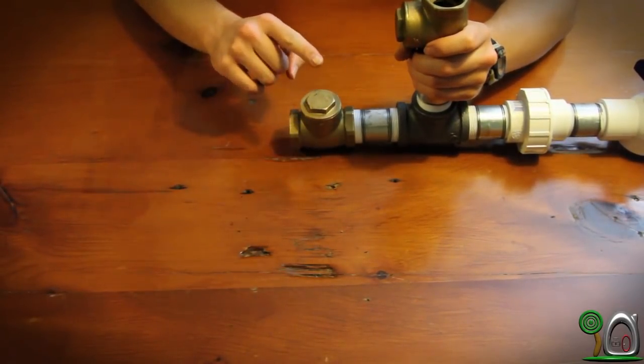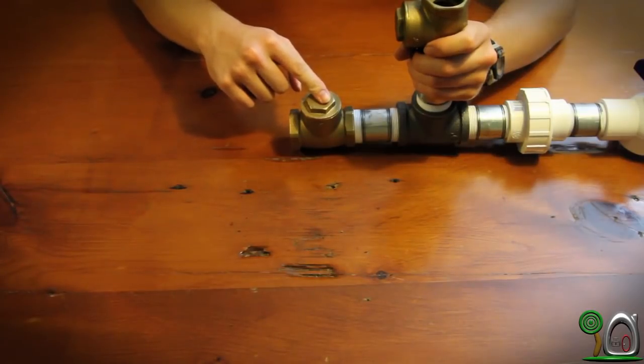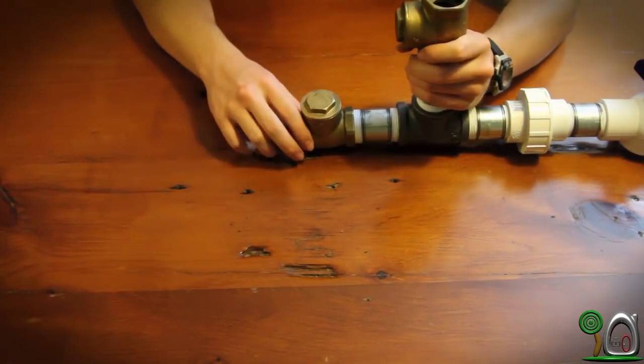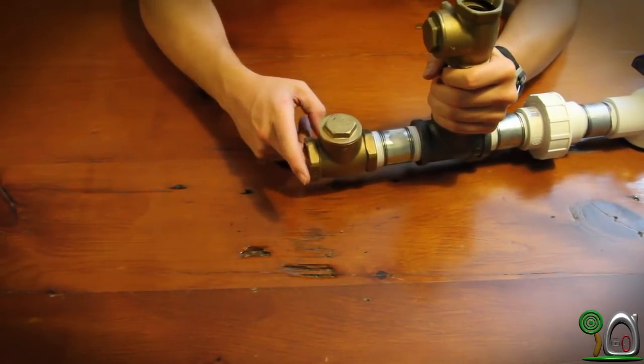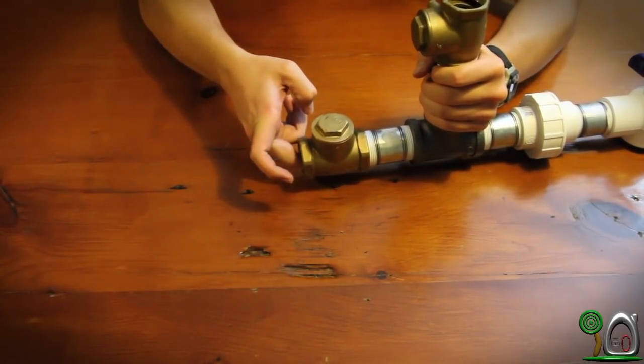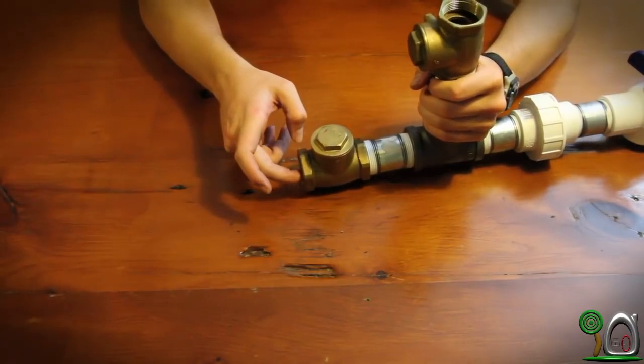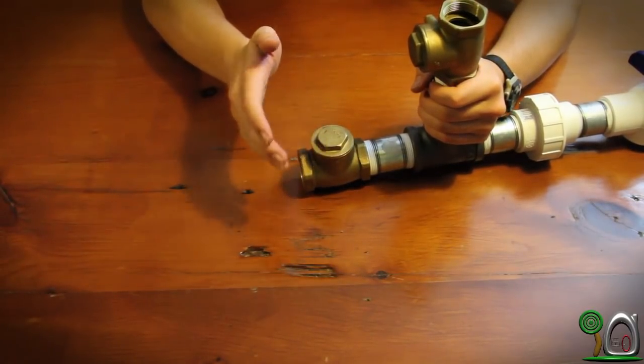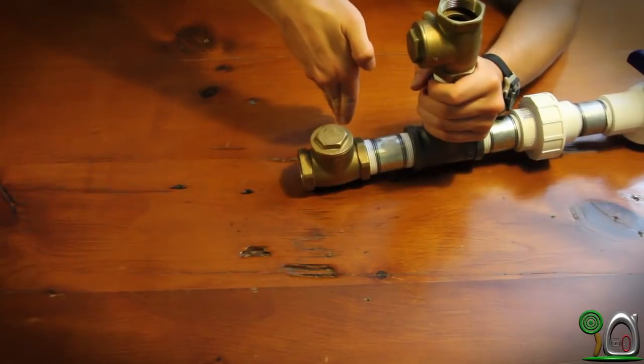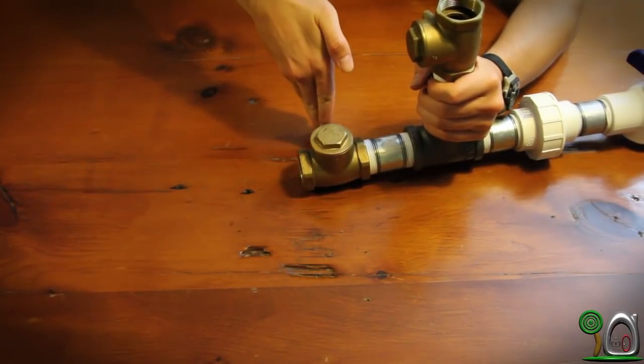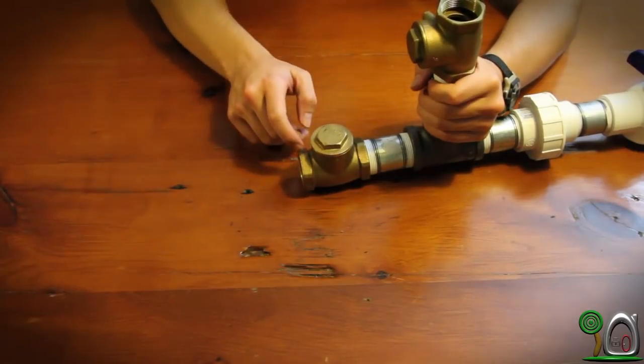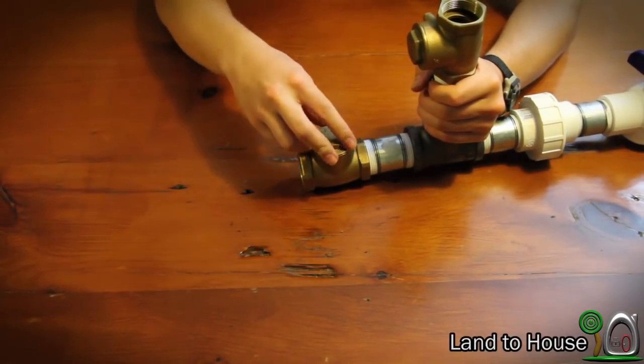because it needs to be closed due to the natural gravity force, so that whenever there's pressure behind here, it stays closed. But when pressure is released, it can easily swing up and then back down. So just make sure that this ball part is facing up.